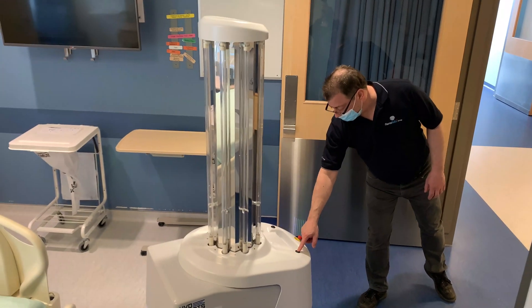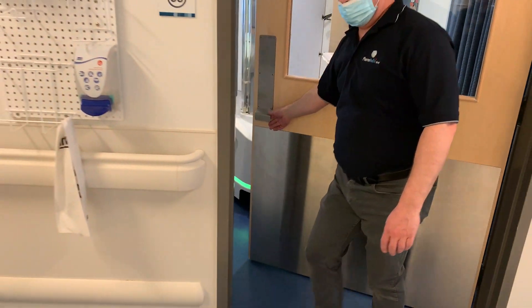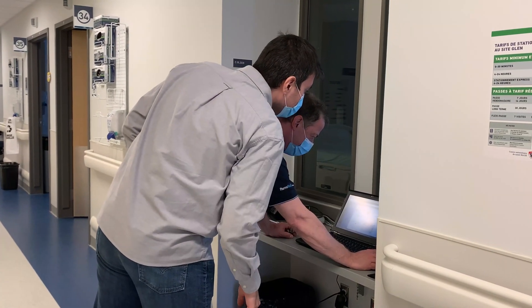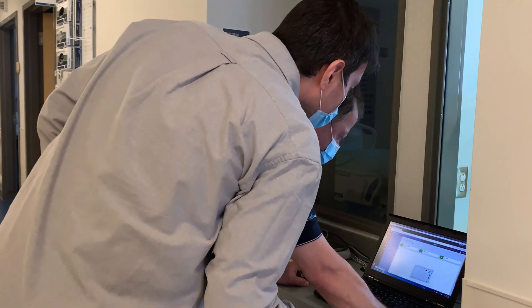The robot has been tested in Europe, it's been tested in China, but we're doing our own testing. Please leave the room, close the door and start the disinfection. So we've got indicators, bacterial indicators and other things that we've put in a room that the robot is actually going to be cleaning. Then we measure what's going on and we can show that the disinfection is at the standard that we want.